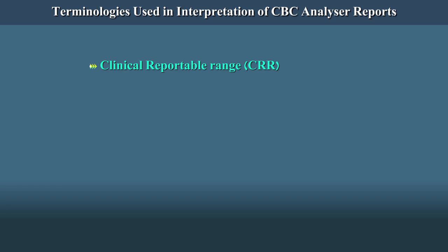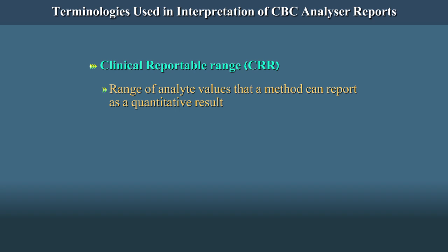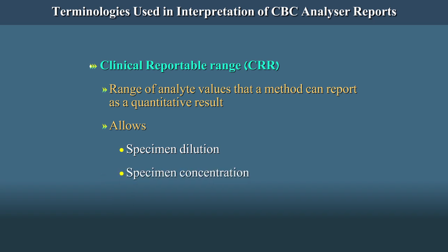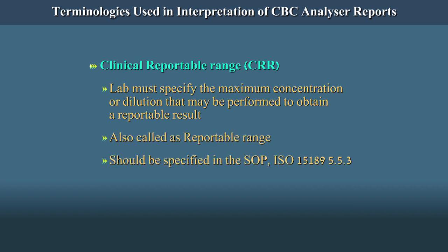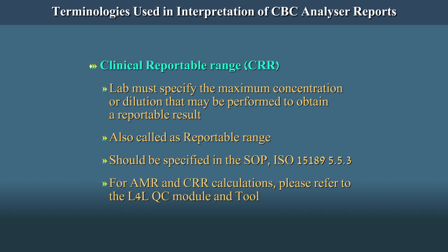Clinical Reportable Range, i.e. CRR. The CRR is the range of analyte values that a method can report as a quantitative result, allowing for specimen dilution, concentration, or other pretreatment used to extend the AMR. The lab must specify the maximum concentration or dilution that may be performed to obtain a reportable result. Also called reportable range, it should be specified in the SOP per ISO 15189 5.5.3. For AMR and CRR calculations, please refer to the L4L QC module and tool.